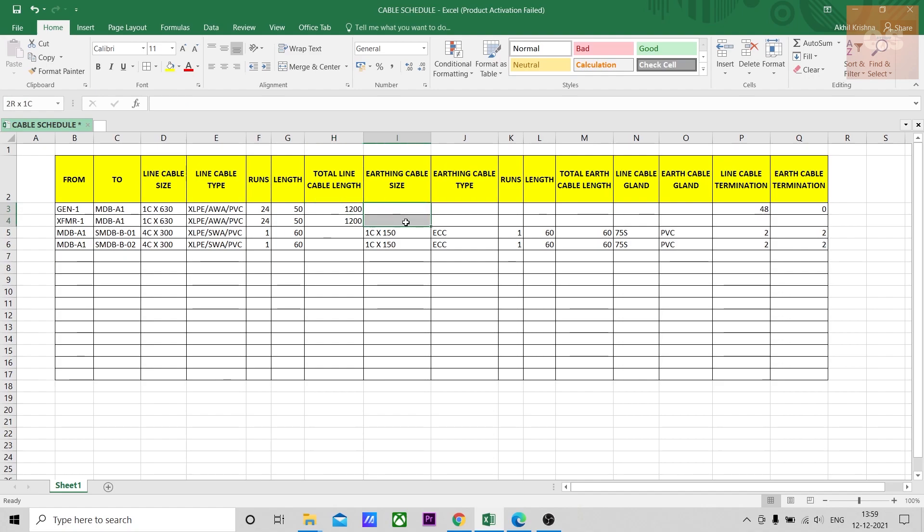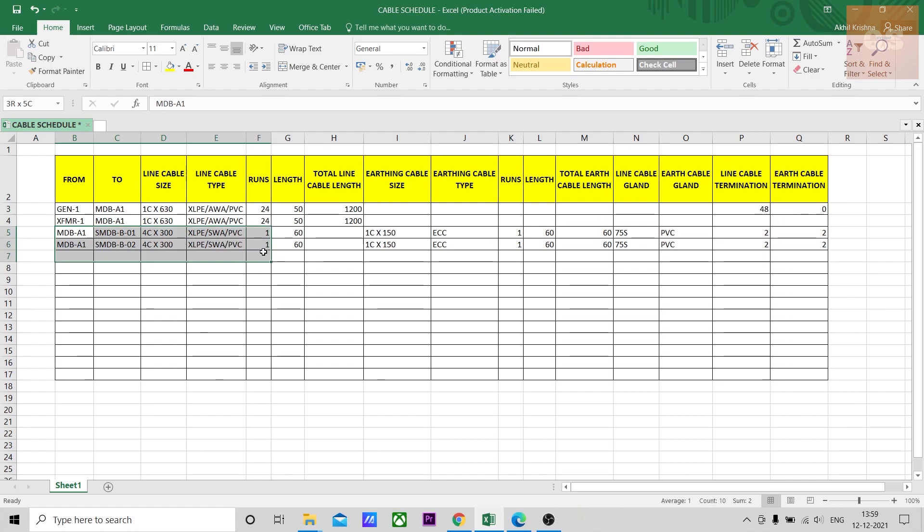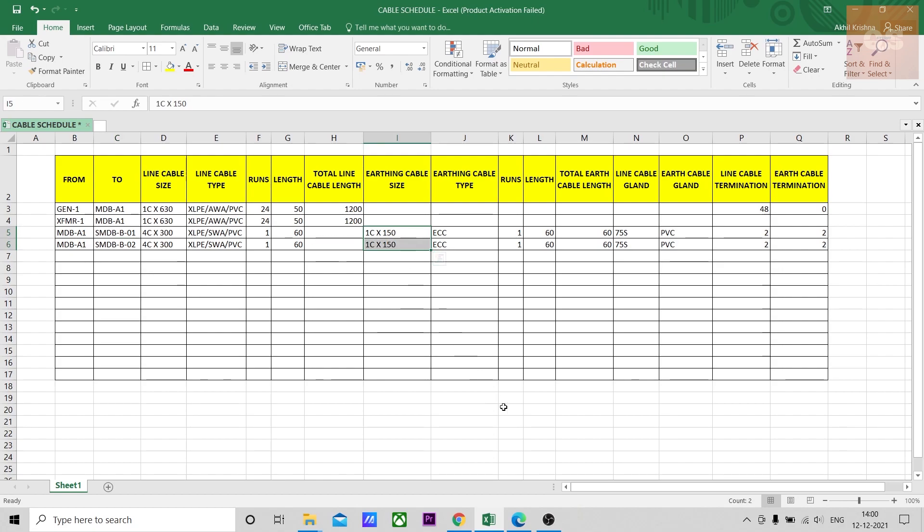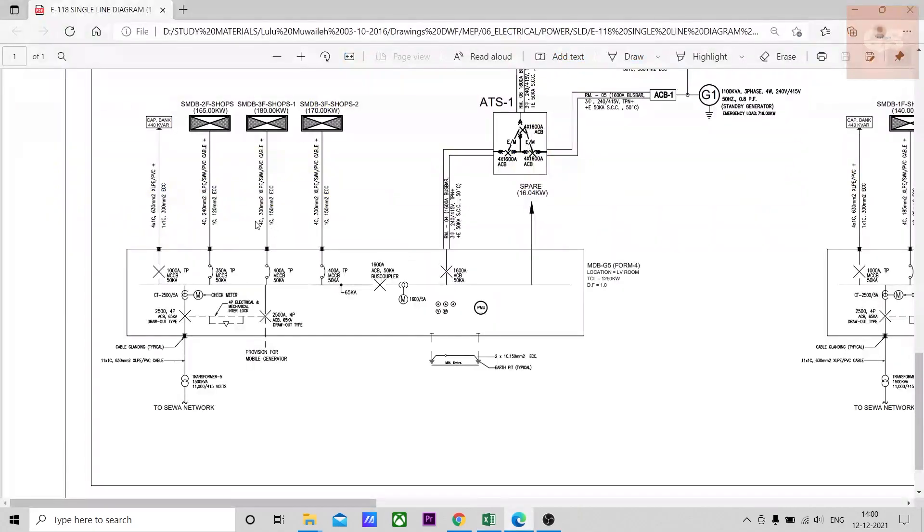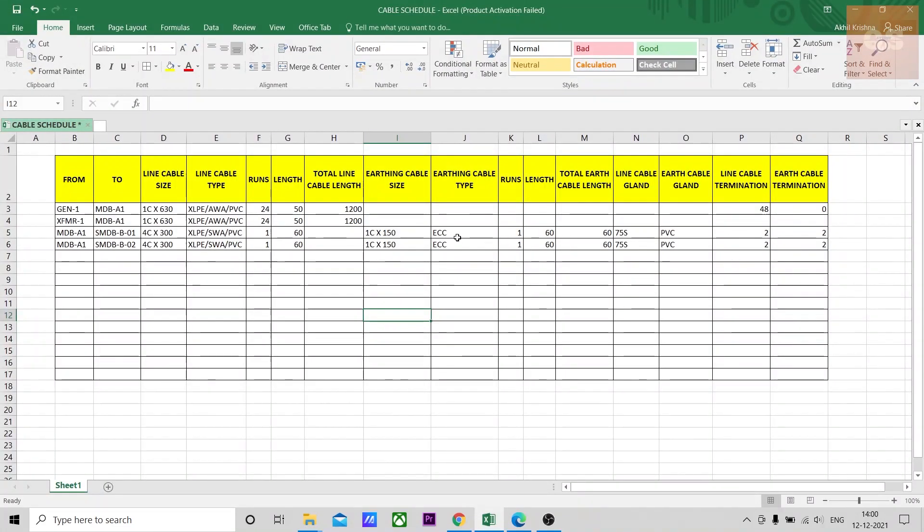Here since it is generator and transformer, earthing cables are not required. For example here it is the length of cable between distribution boards, from the MDB to SMDB, earthing cable will also be mentioned. See four core 300 and then one core 150. ECC, this is the type of earthing cable and all the earthing cable will be one core, one core 150 ECC.